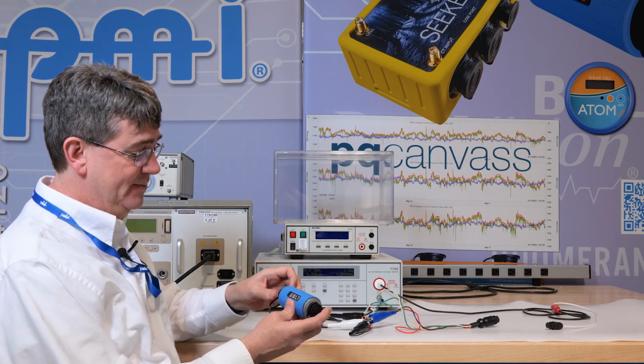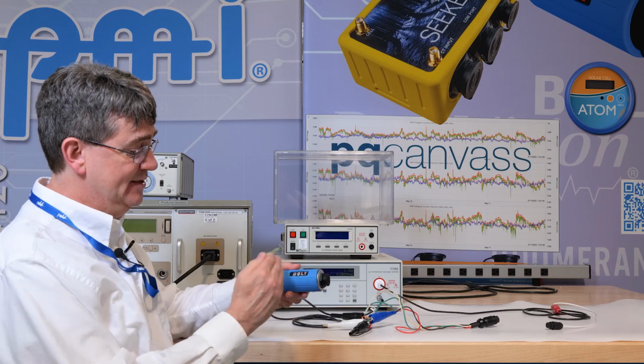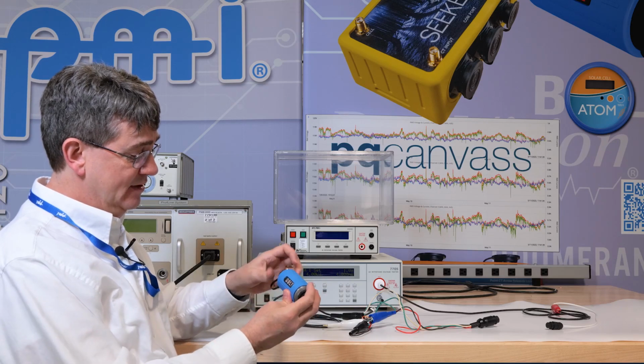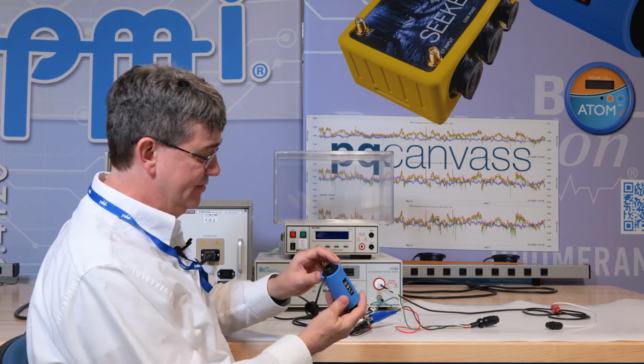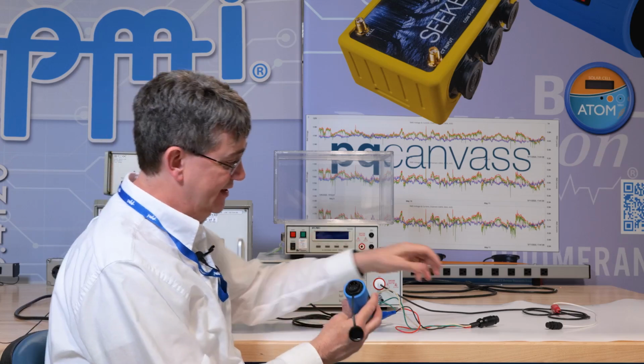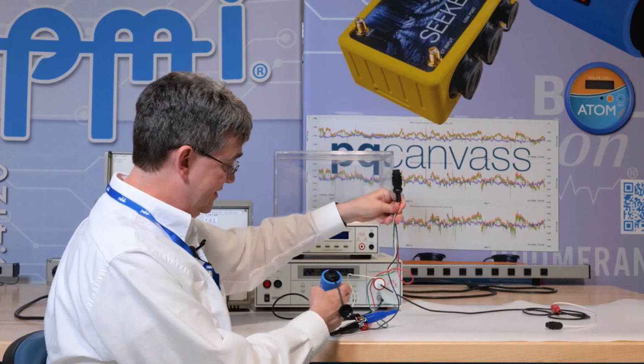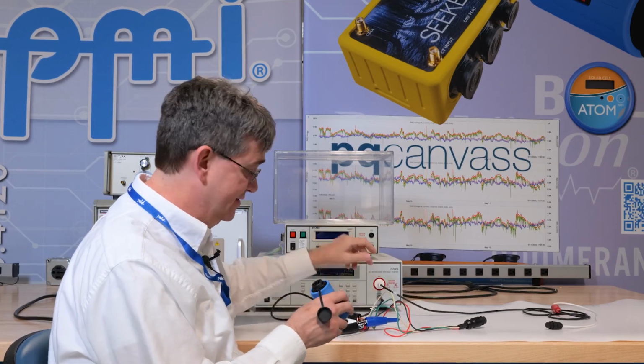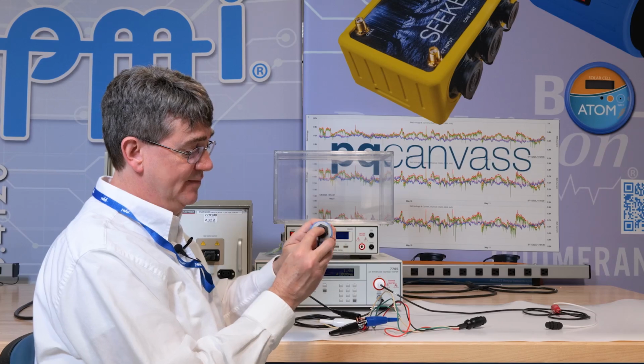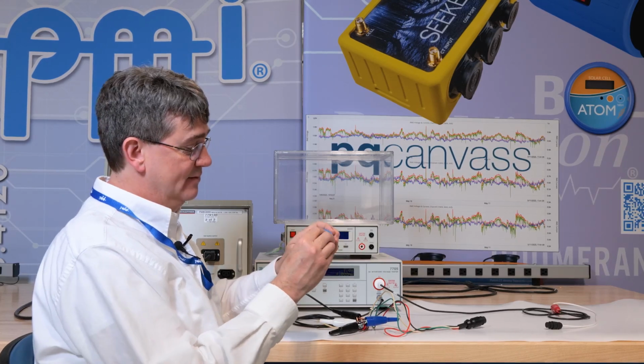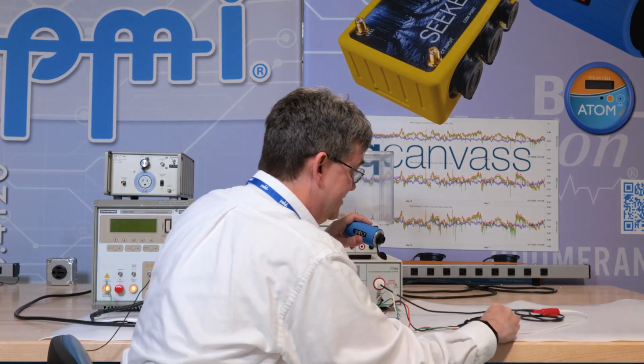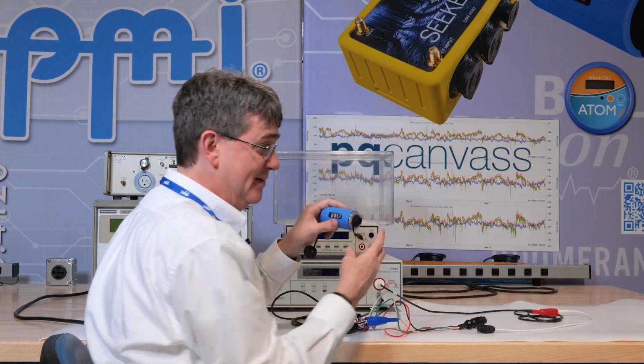In a HiPot test, we apply thousands of volts across the isolation barrier of the bolt. We have a special voltage input lead that connects all the voltage inputs together to one connection that goes to one side of the HiPot tester. Then the user accessible USB and CT connector has a connector that has all the lines shorted together to the other side of the HiPot tester.